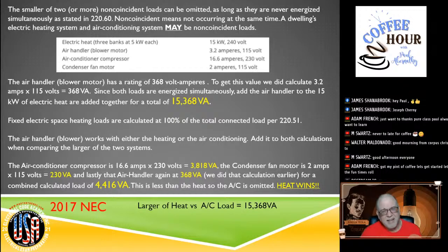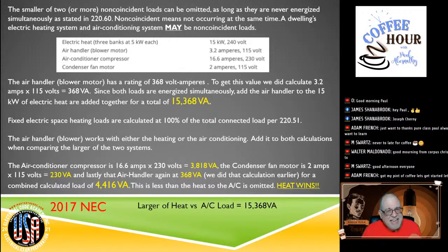When it comes to a dwelling, what in a dwelling is potentially non-coincident loads? Well, because of thermostat control, and again, that's why you've got to be careful. Because if you have a heat pump, then they're not non-coincident loads, because you could have a heat pump where the heat strips also come on, maybe in defrost mode or something like that. So if that's the case, they're not truly non-coincident loads.